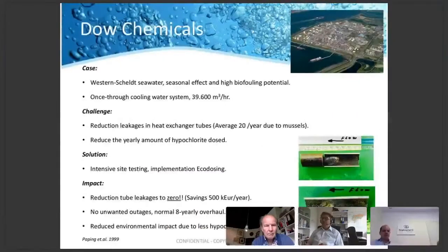Another implementation we did was at Dow Chemicals in the Netherlands. The facility faced heat exchanger tube leakages caused by mussel fouling. Mussels got stuck in heat exchanger tubes and caused erosion corrosion. Dow Chemicals also had a continuous chlorination in their system. We switched it to the Ecodosing regime, and the effect was far more efficient. It resulted for Dow Chemicals in a reduction of leakages caused by mussel fouling to 0.